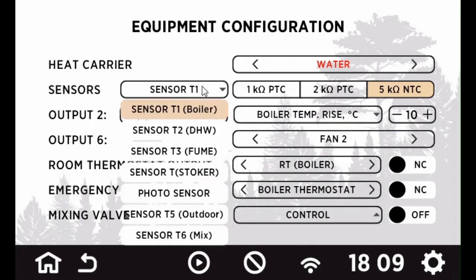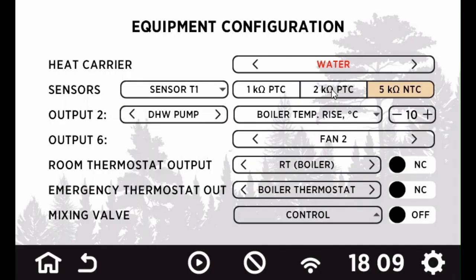In this tab, all the sensors connected to the controller drop down. You can change their type according to what you currently have available. Convenient for service technicians. It is not always exactly our sensor that needs to be installed, well, the one that is installed from the factory. But you can use third-party sensors and they will work. Just remember to reassign them.